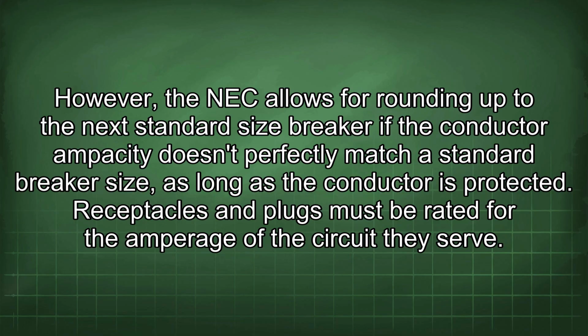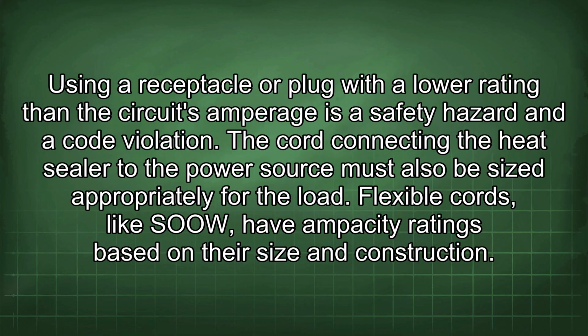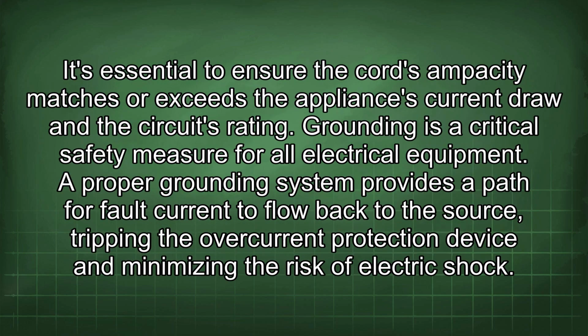Receptacles and plugs must be rated for the amperage of the circuit they serve. Using a receptacle or plug with a lower rating than the circuit's amperage is a safety hazard and a code violation. The cord connecting the heat sealer to the power source must also be sized appropriately for the load. Flexible cords, like SJ, have ampacity ratings based on their size and construction. It's essential to ensure the cord's ampacity matches or exceeds the appliance's current draw and the circuit's rating.